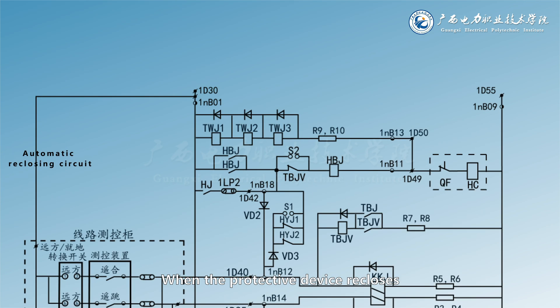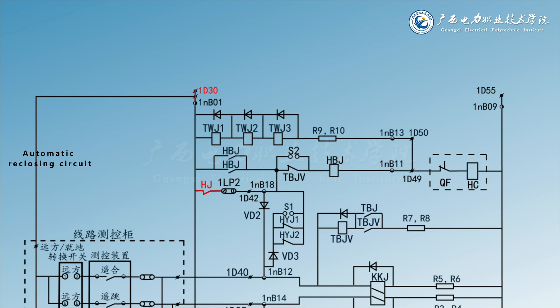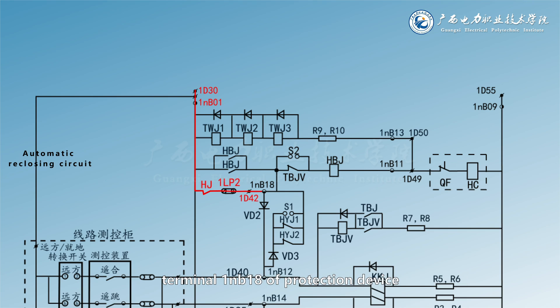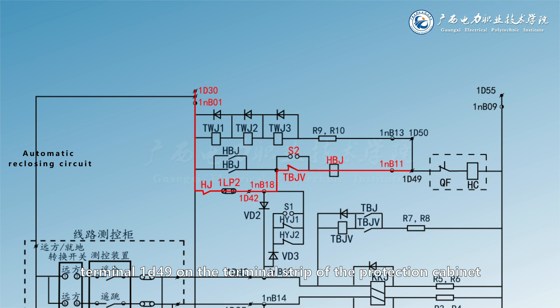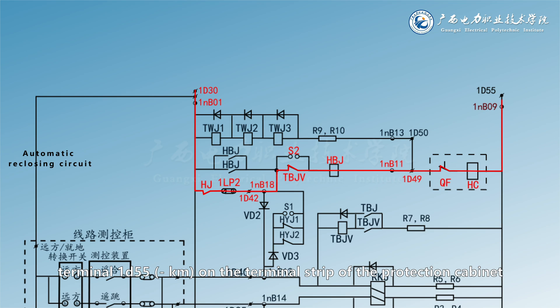When the protective device recloses, its closing contact HJ is closed. Therefore, the closing current path is terminal 1D30, 1NB01, HJ, 1LP2, 1D42, 1NB18, TBJV and S2, HBJ, 1NB11, 1D49, QF, HC, 1NB09, 1D55. So the circuit breaker was closed again.